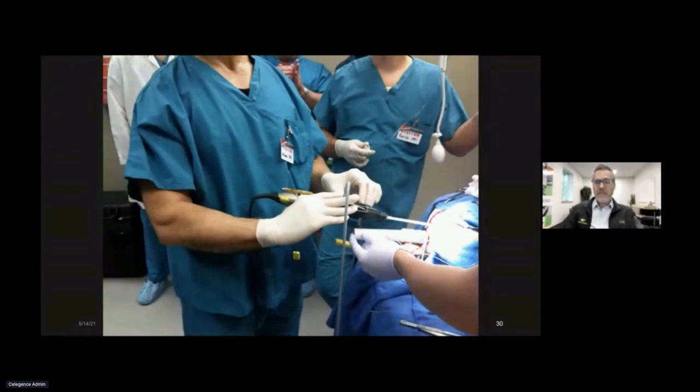Look at how the user's posture and hand position changes during this part of the procedure. Okay, everything changed. You can see how that would be stressful. You could even see the muscles tensed in the user's arm as they're trying to hold the device in this orientation for an extended period of time. All important things. See, we're not just looking at how the device works. Okay, we're looking at everything in the interaction between the user and the device.